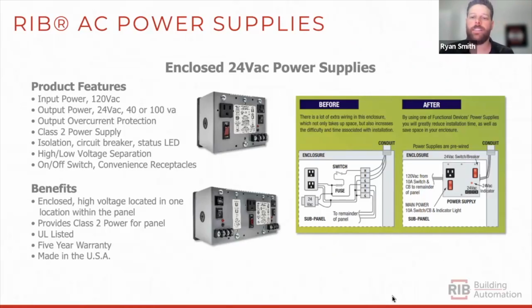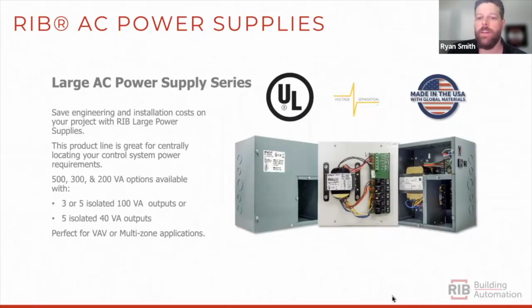This new RIB device fits into our expansive offering for control panel power supplies. Some devices that already fit into this category are the PSH line of power supplies. Considered the gold standard for power supply products, these feature-rich devices can include breakers, switches, high-low voltage separation, power outlets, indicator LEDs, and range from 40 VA to 100 VA in single or dual power supply applications. Functional Devices is your trusted partner for large power supplies as well. We manufacture these large power supplies for multi-zone and VAV applications.